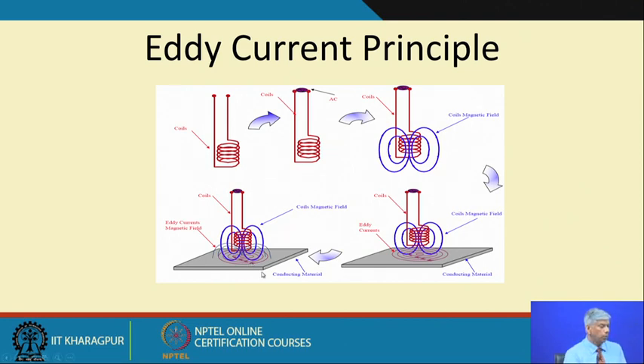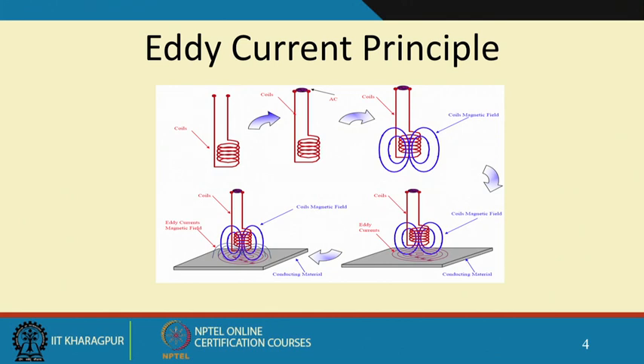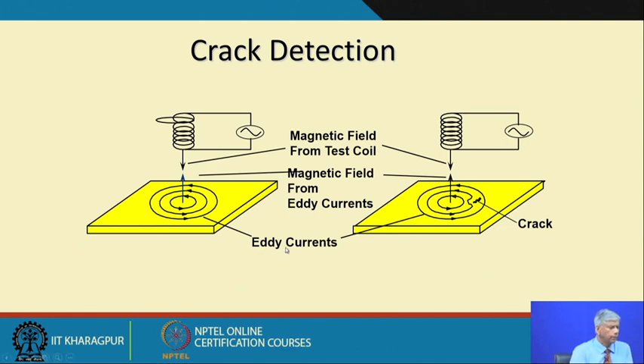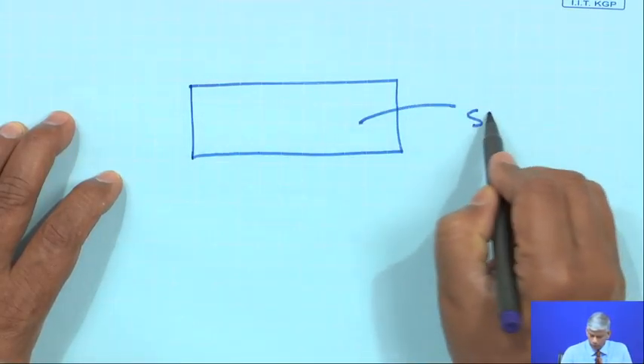The basic principle of eddy current is that the material must be conducting, unlike ultrasonic waves which can pass into any material. To detect a crack, I have a magnetic field from a test coil which I move close to the surface. The eddy current magnetic field is generated, and if there is a crack the intensity or magnitude of this eddy current is going to change qualitatively — this change can be sensed in the voltage measuring device, making it a very easy way to find out surface cracks.